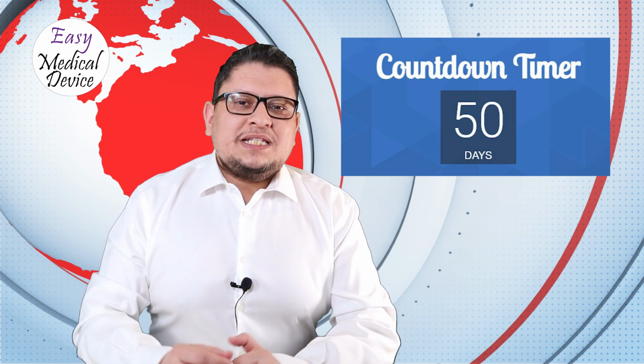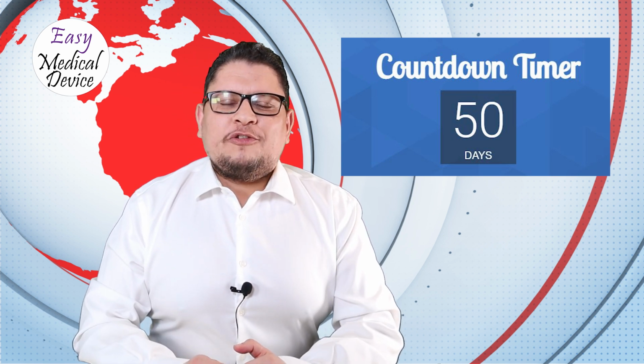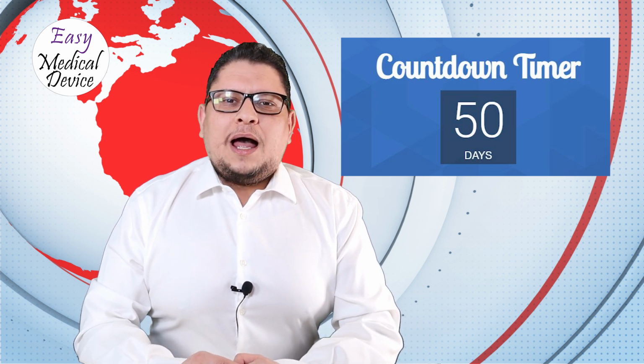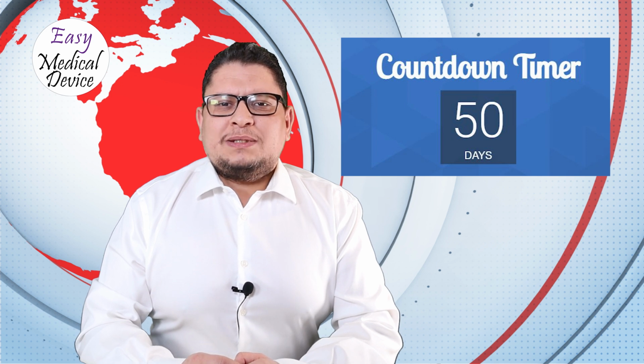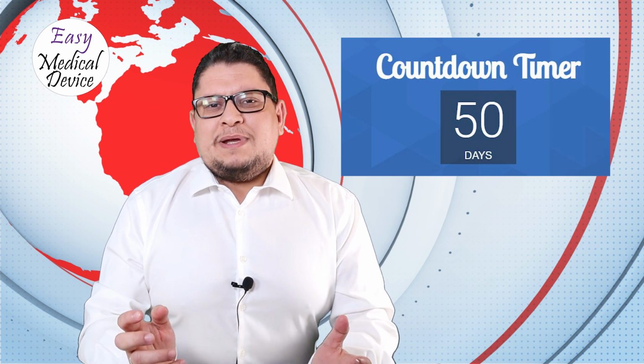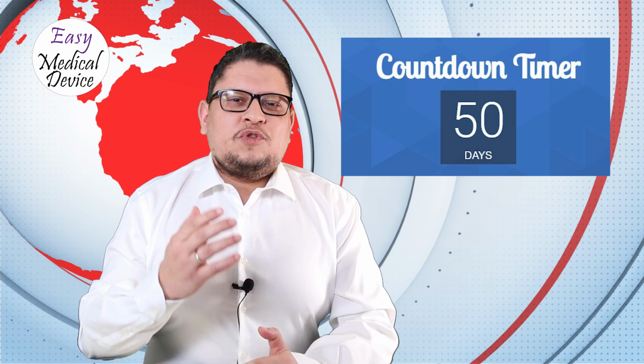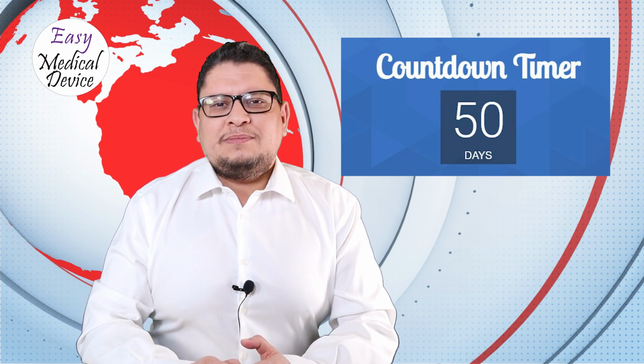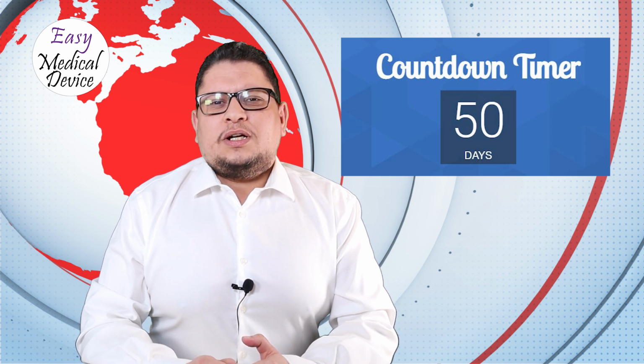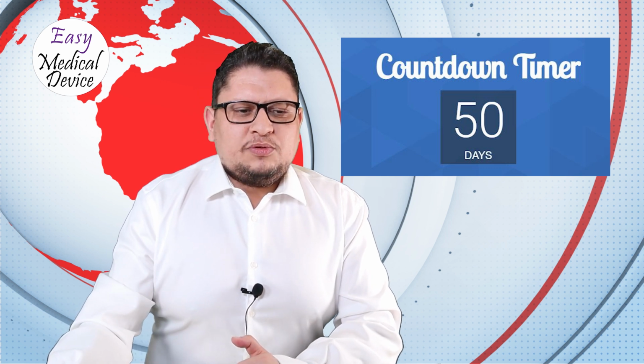If you are a custom-made device class 3, you also have until the 26th of May 2021, so still 50 days, so that you have a notified body that is reviewing your quality management system and that you can have it available. So this is mainly the situation for you, and for the others, if you already have a certificate that is valid under MDD, then you can benefit from a longer transition period. So don't hesitate to really focus on that and to work on it, because it's really something important for you.